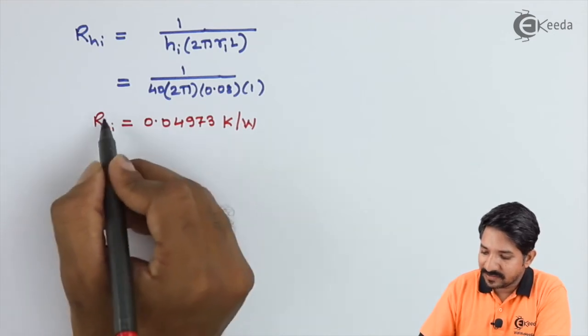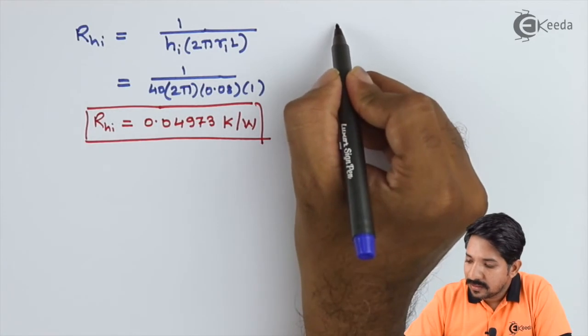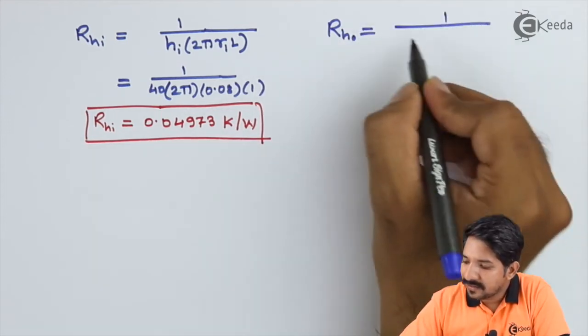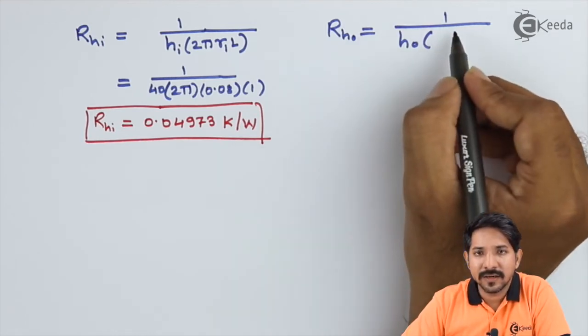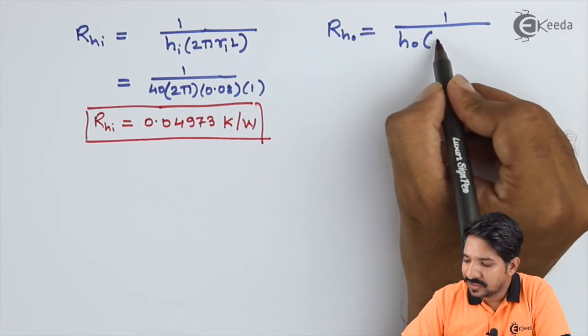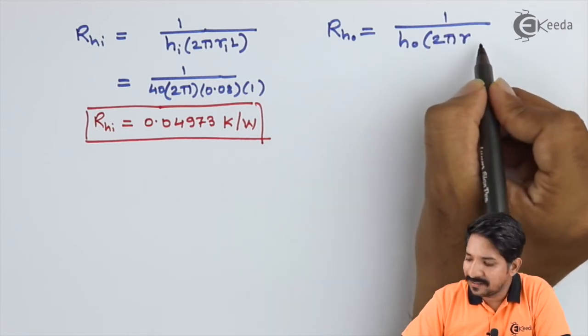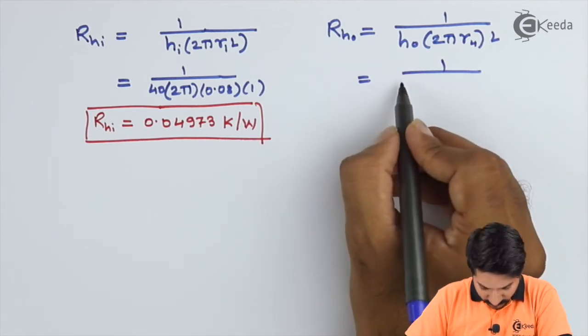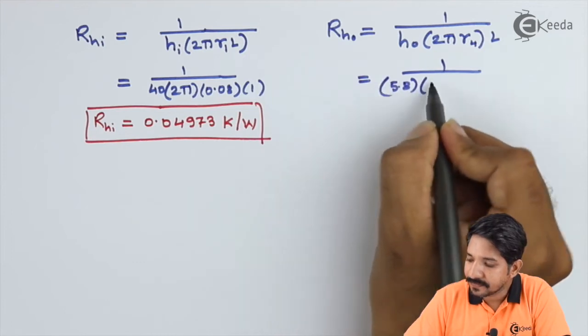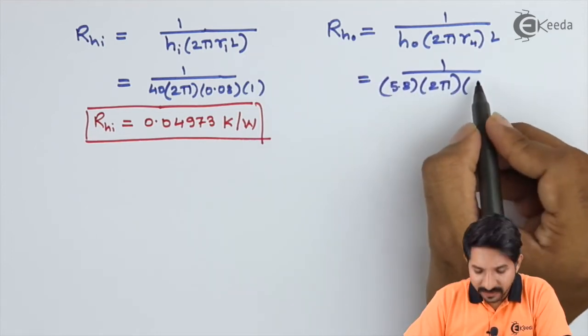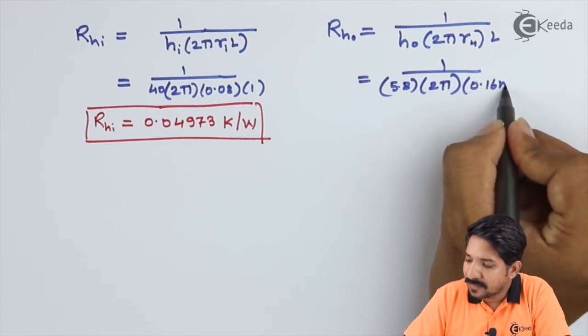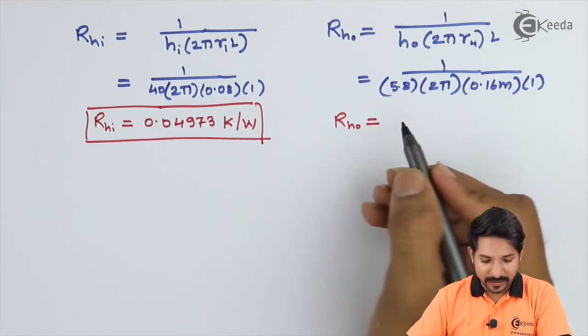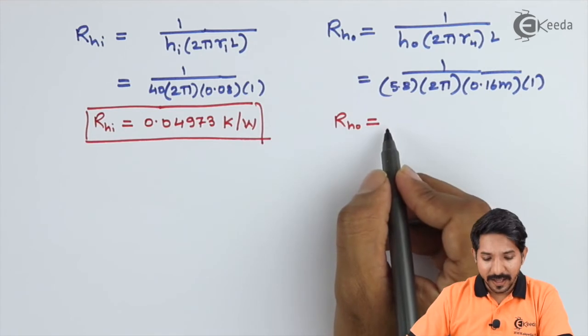Next, finding RHO — the thermal resistance offered by the ambient air. The formula is 1 / (HO × Area), where Area = 2π·r4·L. Substituting: HO = 5.8, r4 = 0.165 m, L = 1 m. Therefore RHO = 1 / (5.8 × 2π × 0.165 × 1) = 0.1663 K/W.